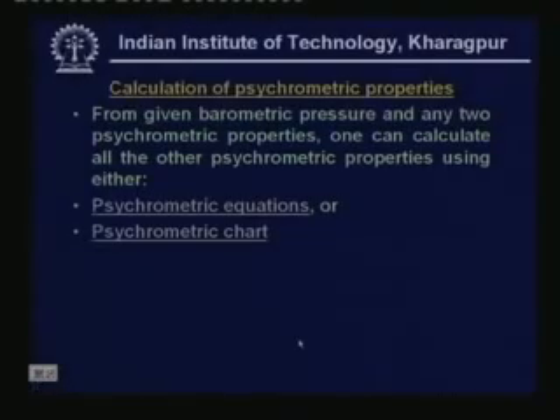Okay, so reading from the psychrometric chart, even though it is easy, can give rise to error if you are not reading the values properly, or if you are not doing the interpolation properly. Okay, so for calculation purposes, it is best to use the psychrometric equations, because they will give you the correct reading. Of course, in the absence of psychrometric equations, one can use the psychrometric chart. Okay. So this is how one can calculate the psychrometric properties.